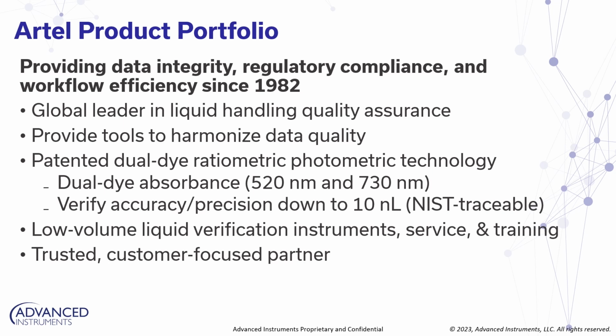Artel's technology is based upon dual dye ratiometric photometry, which simply means that the test liquid contains two distinct dyes, one blue and one red, with absorbances measured at 520 and 730 nanometers. The concentration and ratio of the two absorbances are used to calculate the dispensed volume. Inherently, the method does not require stringent environmental controls and therefore is very well suited for low volume verification. I'll show you a quick animation to accompany this explanation on the next slide.